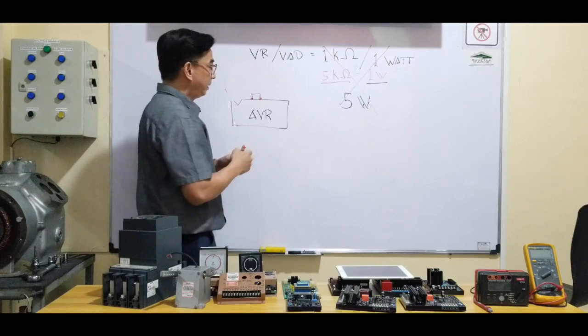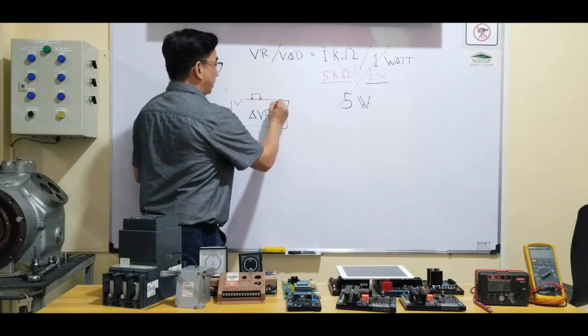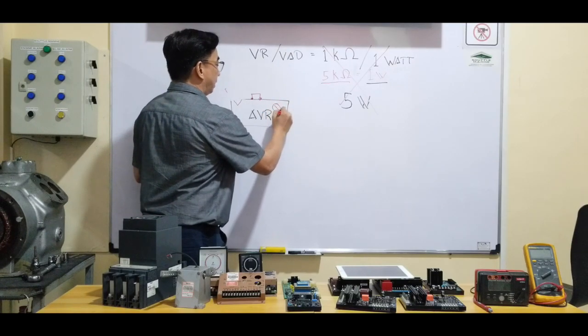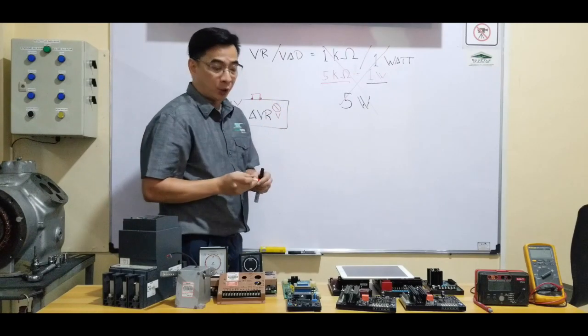So if I don't have the spare potentiometer, I'll just install this jumper. And I'll be adjusting the voltage of my alternator via AVR voltage trimmer.